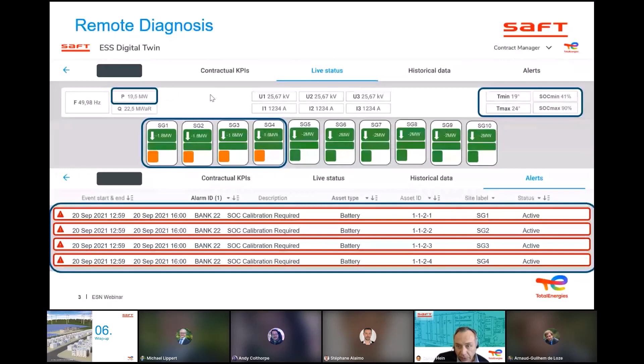And now this SOC calibration flag means that the value of the state of charge and the available energy communicated to the energy management system might be the incorrect one. And that is what created this issue. So in order to recalibrate the state of charge, the affected battery banks needed to be isolated.